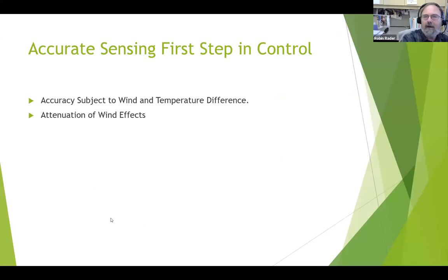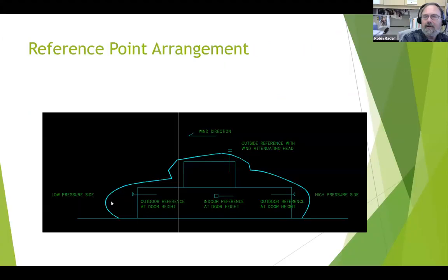Okay, so now we're going to talk about accurate sensing of building static pressure. Static pressure sensors are subject to wind and temperature difference. So we're going to talk about attenuating the wind effects. Here's a picture of a building with wind blowing from the right to the left. And so we have a high pressure side on the right. The wind pressure envelope goes over the building and off to the left.